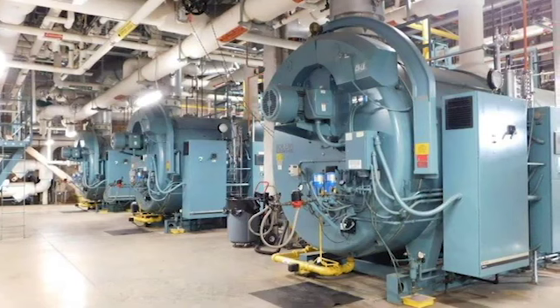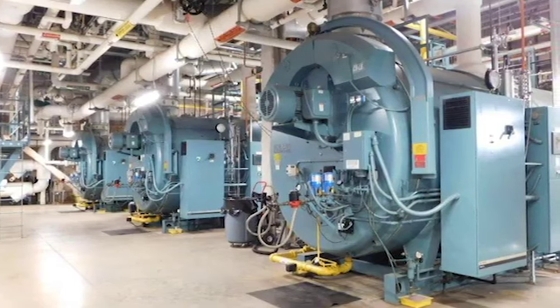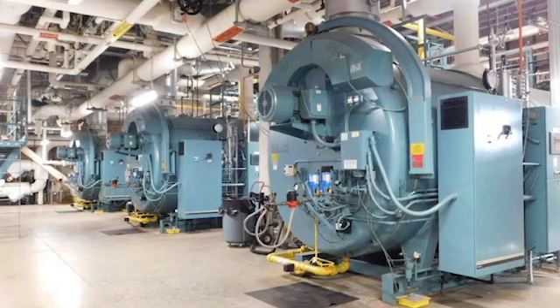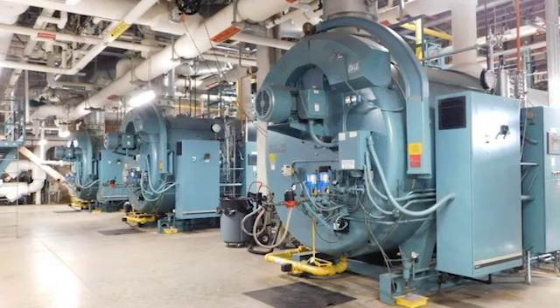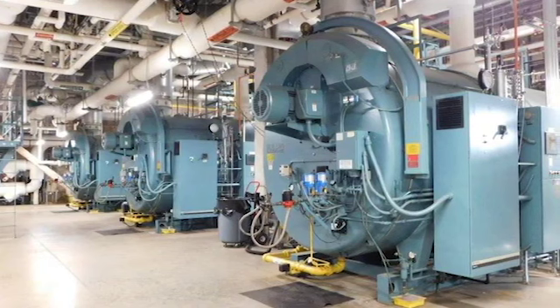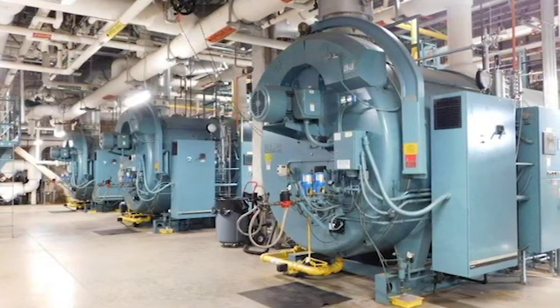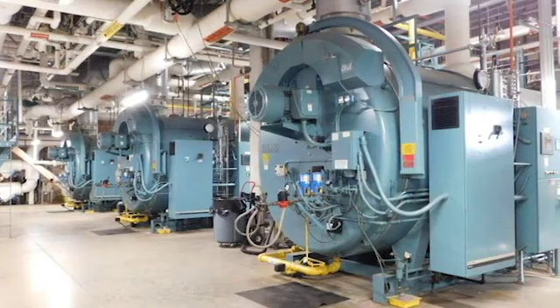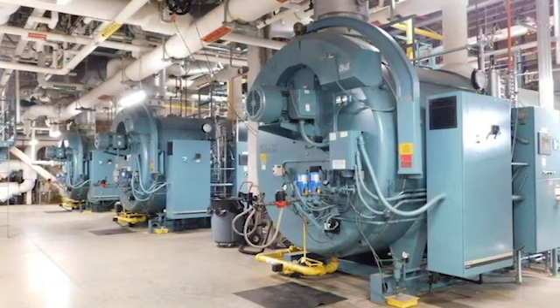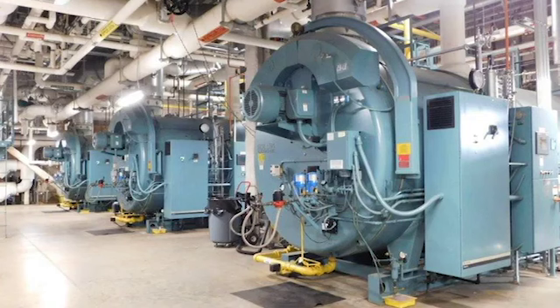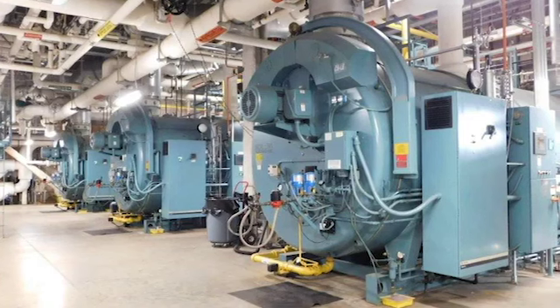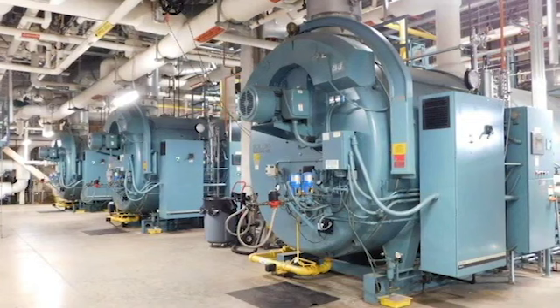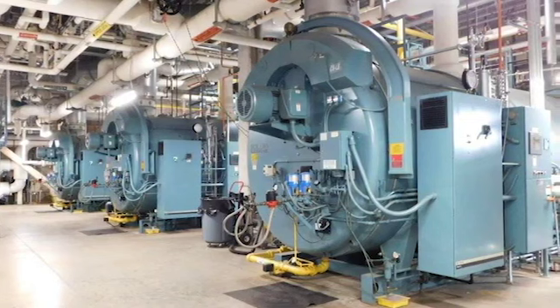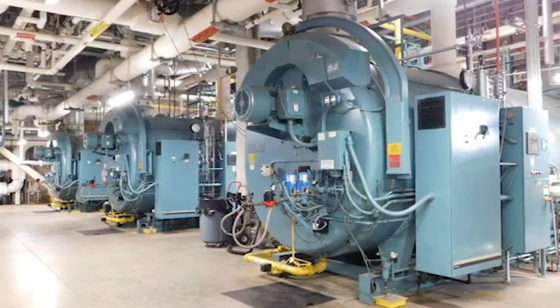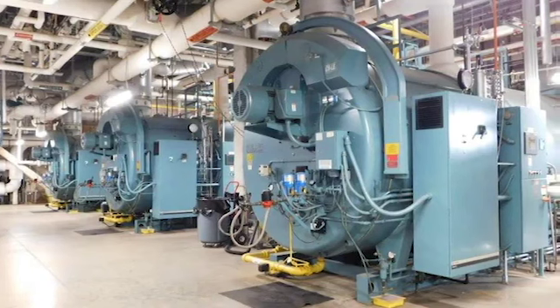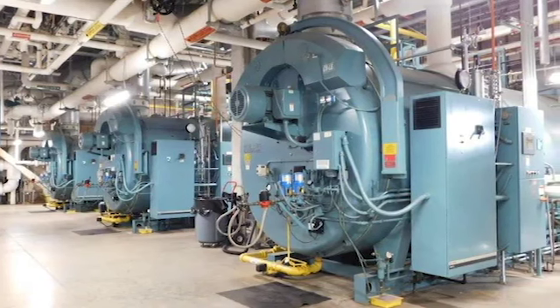Each boiler does about 20,000 pounds an hour of steam at about an 85% fire. Primary fuel is natural gas, but secondary fuel is fuel oil. We test monthly to make sure that the operators are always able to run on oil. We don't want to have a fire drill, God forbid there was a gas interruption. It has happened, although it is very rare to lose your natural gas. We're prepared for it if it does happen, and we can take care of the hospital and their critical mission.